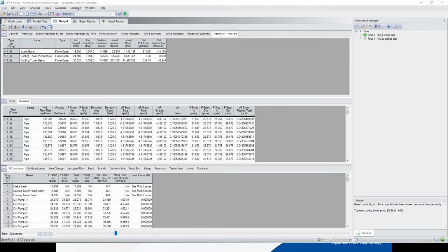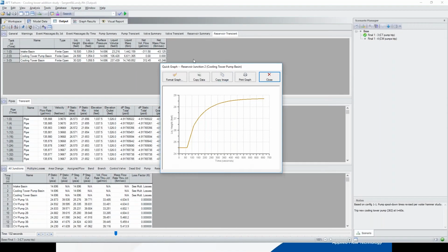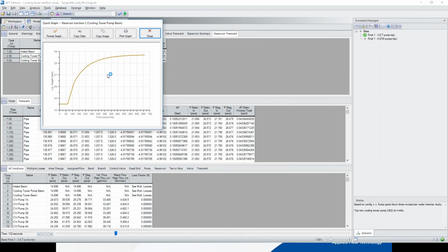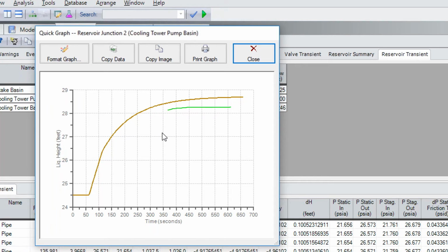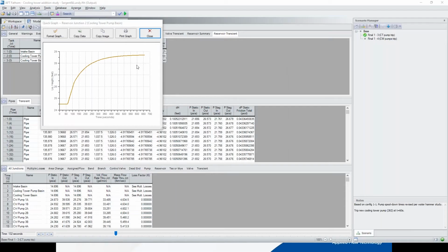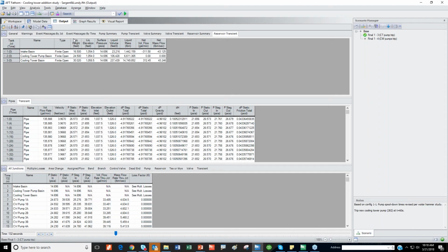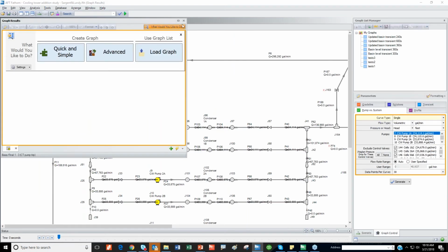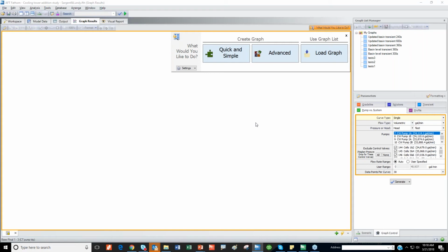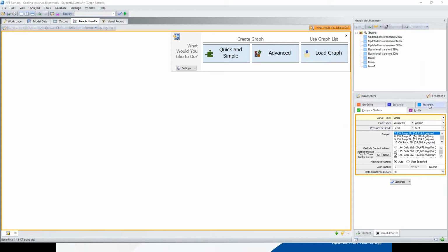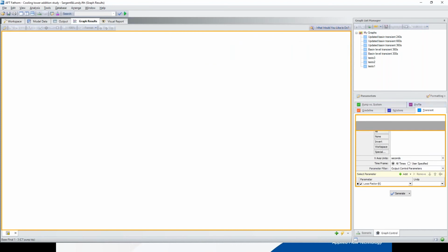So now we're going to go to the transient for the reservoir, and we select transient reservoir, and we have here the liquid height level that we want to take care of. So we're concerned with the cooling tower basin, and we want to see how the liquid height changes in time. So I select it and ask for a quick graph. And it gives me a graph of how the height of the liquid changes in time. As we said, our limit was 30. So now we see that the liquid height only reaches around 28.5, and our limit would be somewhere up here. So we're okay.